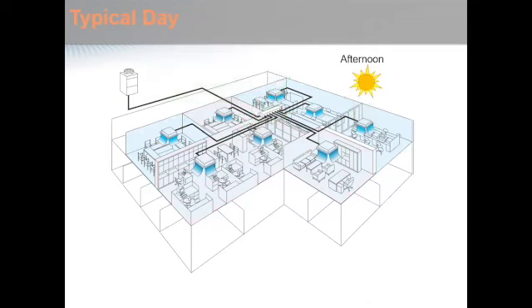So in the afternoon, as the day heats up, all of these zones are going to be requiring cooling, and that's completely acceptable on a heat recovery system. That's one thing I do want to stress. If you go out and start designing around VRF and you use heat recovery, maybe to meet some of the efficiency standards that are coming into the market, or just because you find it good for that application, heat recovery is able to act as a heat pump.